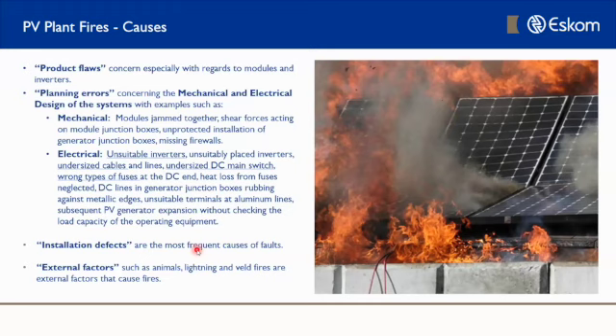Product flaws are a specific cause of PV plant fires, from using products that have flaws. Planning errors are a very prevalent direct cause, where mechanical and electrical design errors are made in the system being installed — remember, we're stringing a bunch of equipment together to provide a system. Some mechanical-side issues have contributed, but the electrical side is much more prevalent: unsuitable inverters, undersized cables, undersized DC main switches, wrong types of fuses, etc., have all been causes of fires.